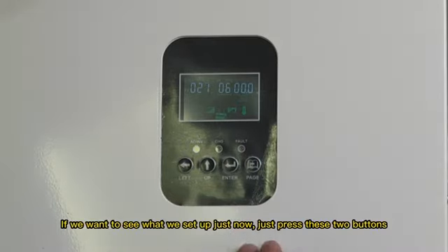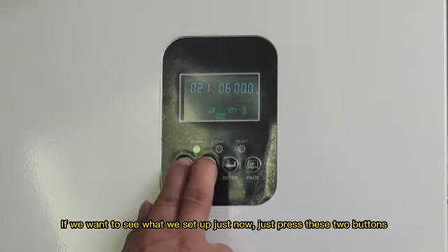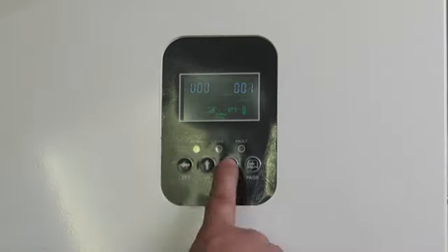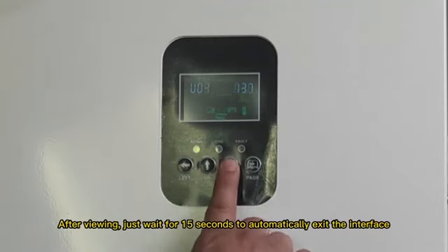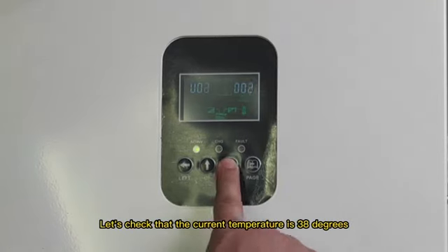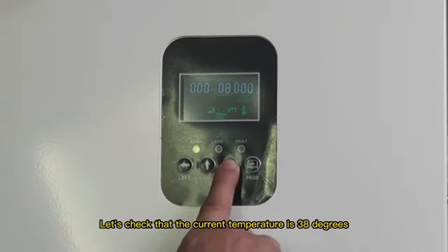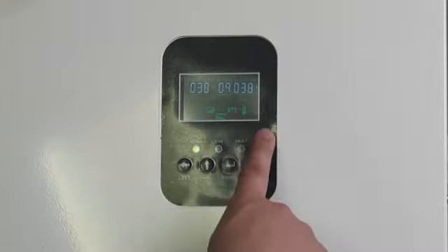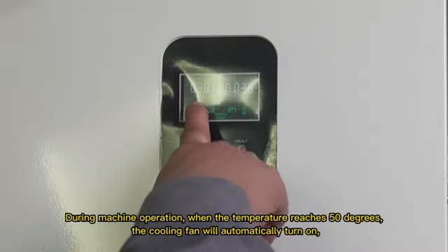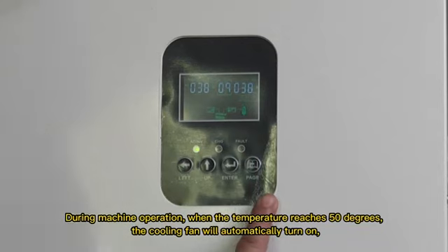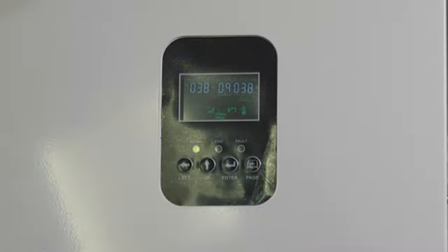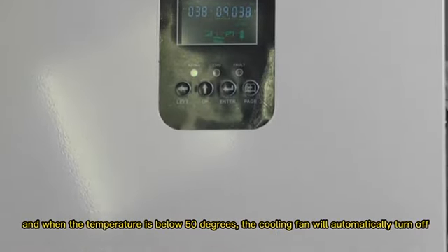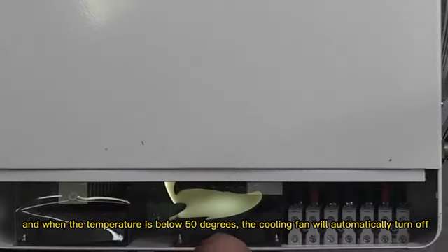If we want to see what we set just now, just press these two buttons. After viewing, just wait for 15 seconds to automatically exit the interface. Let's check that the current temperature is 38 degrees. During machine operation, when the temperature reaches 50 degrees, the cooling fan will automatically turn on. And when the temperature is below 50 degrees, the cooling fan will automatically turn off.